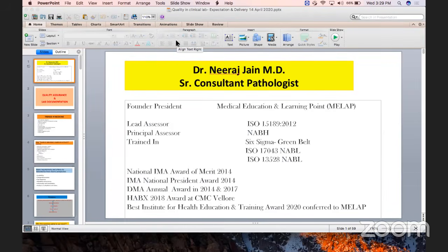Sir, the next question is regarding IQ, OQ, PQ frequency, should it be done every year or only when the instrument gets installed? No. IQ is installation qualification, when you are purchasing an equipment. Operational qualification, whenever you are appointing a new person who is not trained, you arrange training for that person to operate that machine. That training may be through a company person, or some already trained person can also train a new person. This precision, linearity and carryover shall be checked once in 12 months.